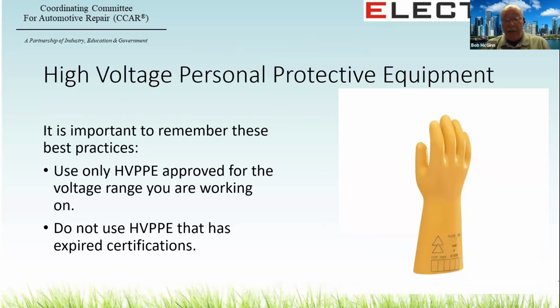All qualified high voltage PPE will have a voltage range and an expiration date. This applies to gloves, boots, sleeves, aprons, all of the rubber PPE. Most of this is previously all lineman's PPE. It's important to use the correct high voltage rating and to have your personal protective equipment recertified by the manufacturer or replaced once it expires.